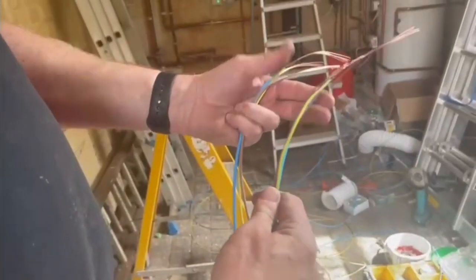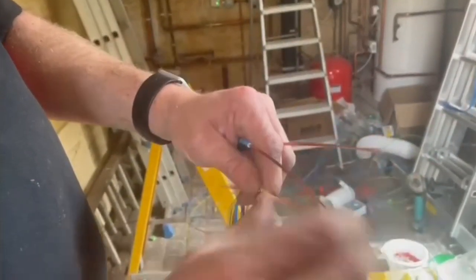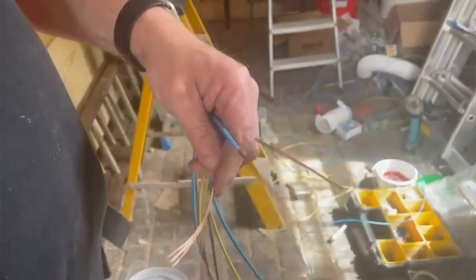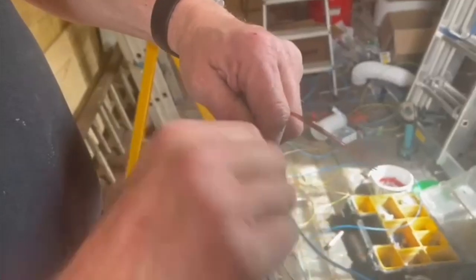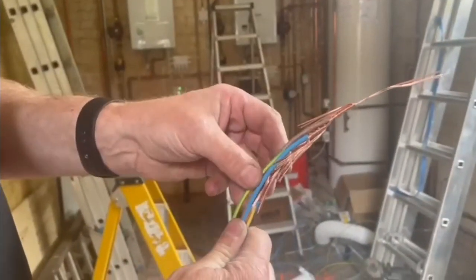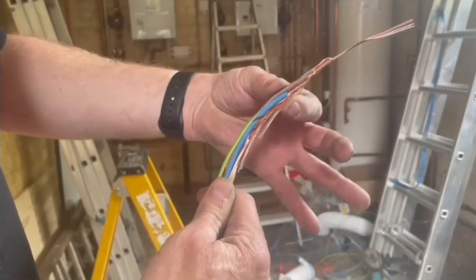So we know the last three coming up the pipe — all these group of cables here. We'll now tie that one onto here, fold it back, put the next one on there, and then we can tie the last one on like that. So now we've got that group of cables there — they slowly build up inside. So as they come in, if they come up against an obstruction, or a bush, or a coupler, it will just slide through slowly.